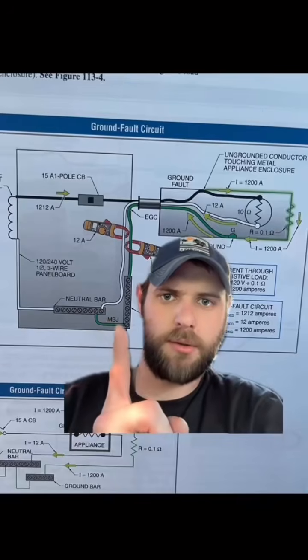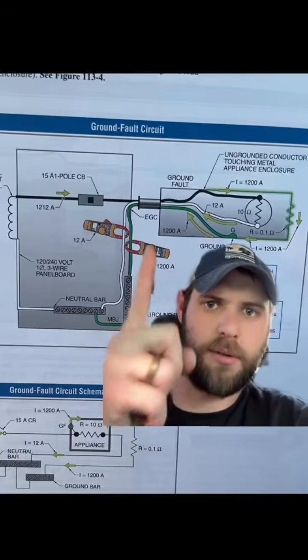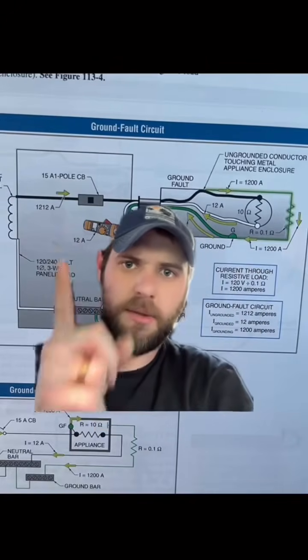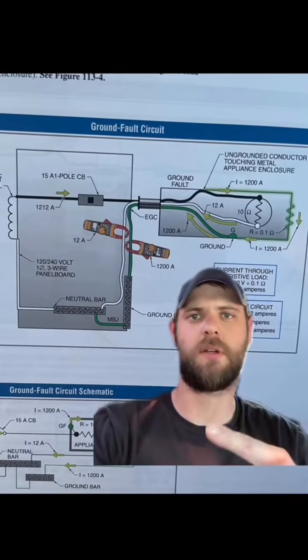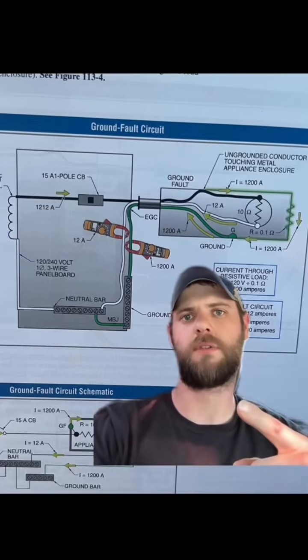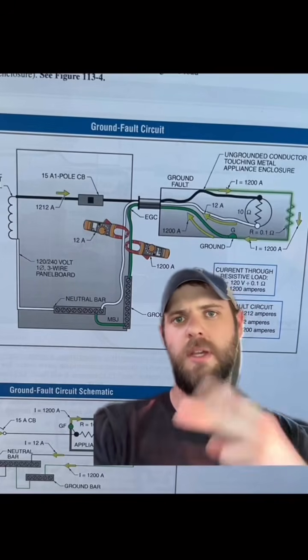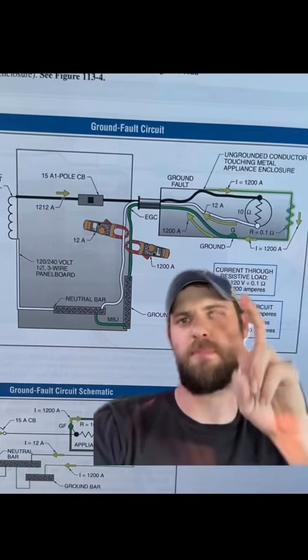We bond our neutral and ground together at the service. That way fault current can find its way back to the power source. A couple of big misconceptions in our industry are, number one, the grounding electrodes are for fault current and making breakers trip, and number two, fault current finds its way back to earth.